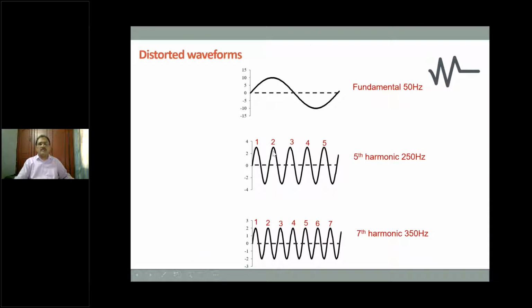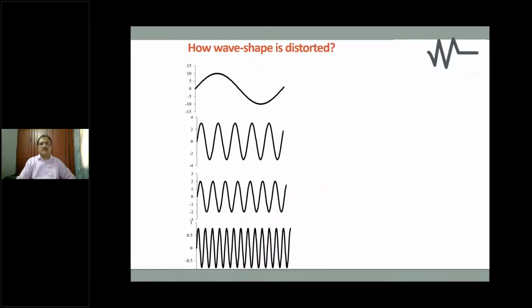So if there are 5 wave shapes within one cycle, it will be caused by the 5th order harmonic. If there are 7, it will be caused by the 7th order harmonic. And the standard now prescribes that you have to measure up to the 50th order. Right now, the standard is not talking about beyond the 50th order, but there are already some schools of thought on orders up to 100. So we will not bother too much about anything more than the 50th order.